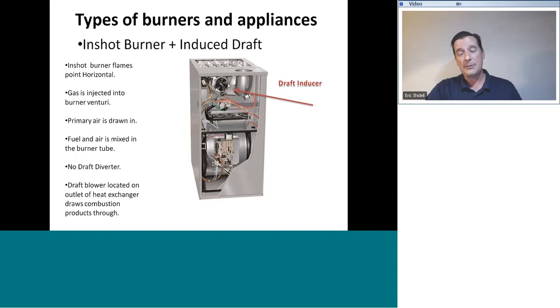Now here is an interesting fact, and this is going to blow you away. Even though this is a fan, and even though the discharge of that fan is going into the vent, into the flue connector, the vent on an induced draft appliance is still negative pressure. Yes. The purpose of the draft inducer is not to force or push combustion products up and through the flue. The job of the draft inducer is to simply deliver the combustion products to the flue. The flue or the vent should still be under negative pressure, pulling those combustion products up and out of the house. Very interesting thing to realize.